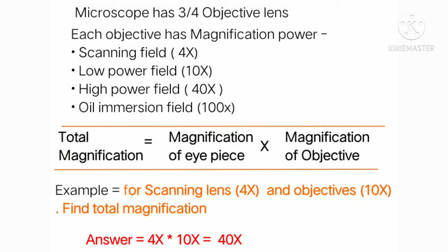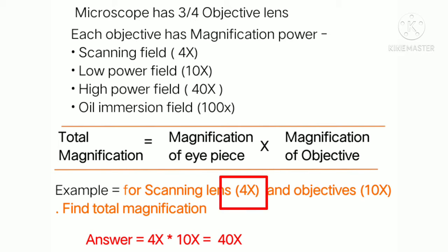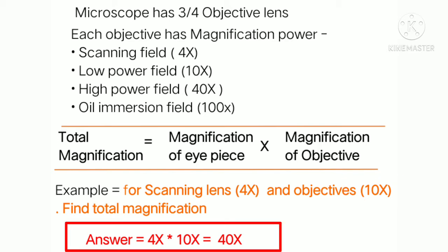A microscope has three to four objective lenses divided into four types by magnification power: 4x for scanning field, 10x for low power field, 40x for high power field, and 100x for oil immersion. To find total magnification, use the formula: total magnification = magnification of eyepiece × magnification of objective. For example, scanning lens (4x) × eyepiece (10x) = 40x total magnification.